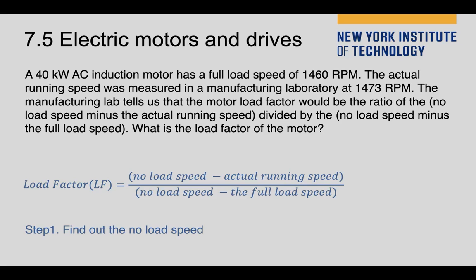But now, what I really measured when the shop is running, we use some meter to measure the rotational speed. That is 1,473. It will have a variance, of course. It will not have an exact number.